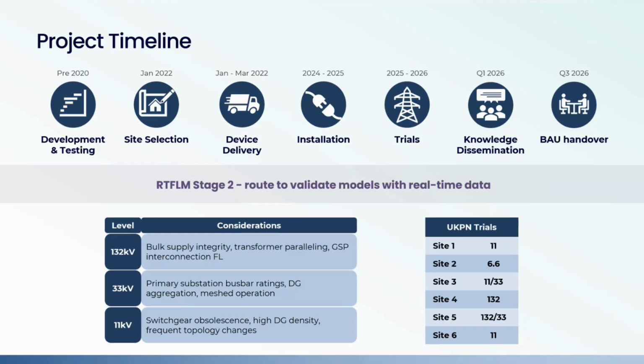From a technical perspective, we validated RTFLM outputs against our computational models. And crucially, that validation happened in real operating conditions, as Ralph mentioned earlier, including live switching outages and network reconfiguration. We also supported the off-network testing through the lab test conducted at an early stage, and the overseas testing using a network-fed fault, which the team will share more information about throughout this presentation. And this is all to stress the network-fed faults, is to stress the device beyond the normal operation.